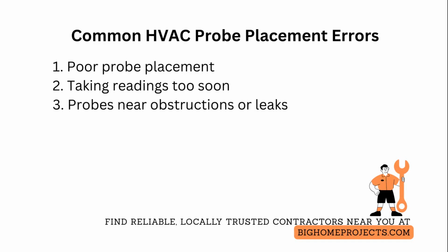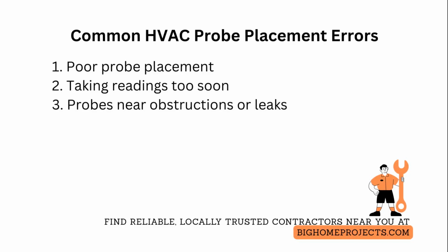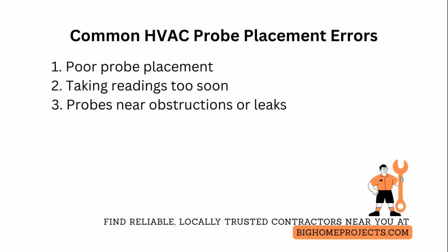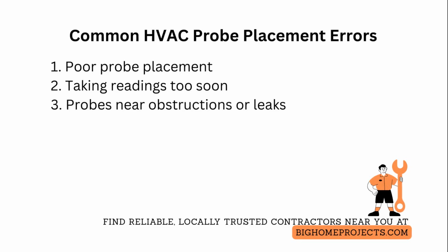One of the most common issues is taking readings too soon during warm-up or shutdown, leading to transient errors that throw off computed airflow CFM. Fix this by waiting a minimum of 5 to 7 minutes at steady-state heat and averaging several consecutive readings.